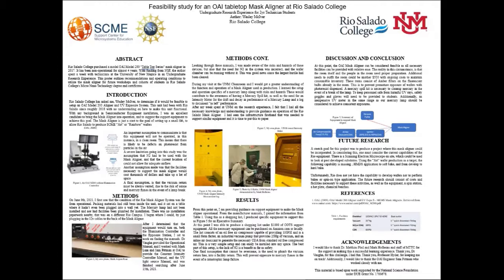At this point, it was determined that the necessary facilities are as follows: two 120 volt 60 Hz AC power outlets, 25 inches of mercury vacuum source, 20 psi of nitrogen, and 60 psi of compressed air. The gas and vacuum lines are made up of 1/4 inch quick disconnect fittings.